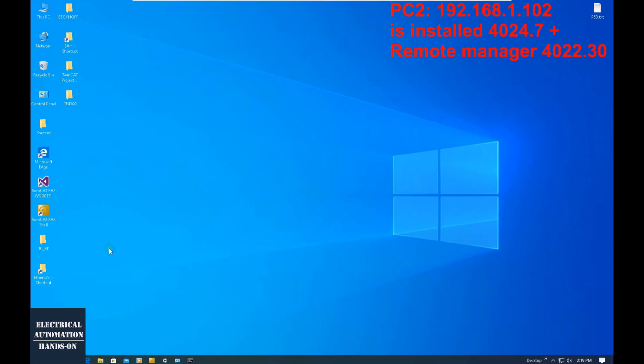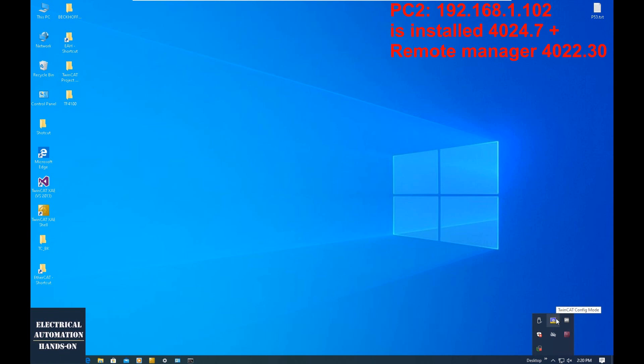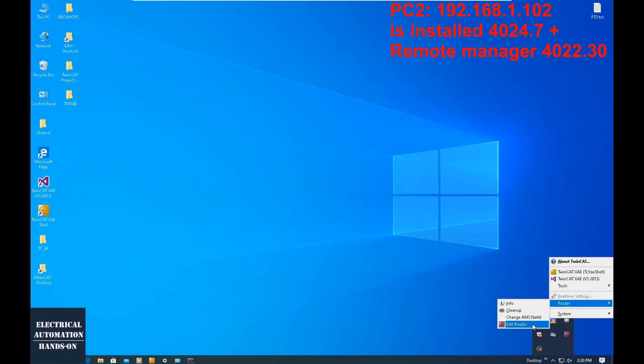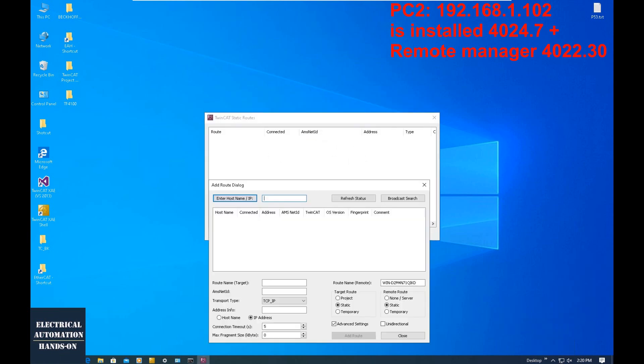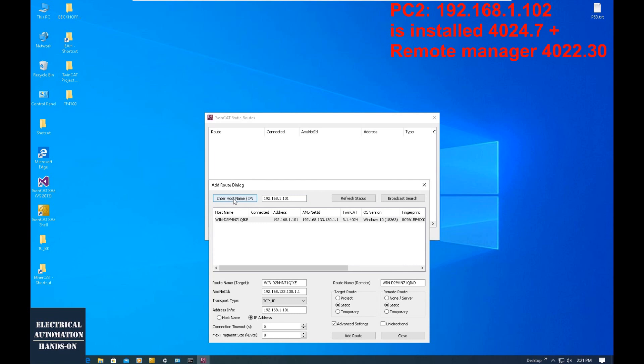This is my second laptop. I already installed the remote manager. My current version is TwinCat 3 3.1 4024.7, and I also installed 3.1 4022.30 as the remote manager software. Firstly, we need to guarantee we can connect to that controller. So we find the TwinCat config mode icon, right-click, click router, then add the routers. He just adds the IP address of the remote controller — that is 192.168.1.101 — and enters the host name and IP. Once it shows up here, that means this laptop already found one remote controller. This is the remote controller name, this is the IP address, and this is the AMS Net ID number running inside that controller.